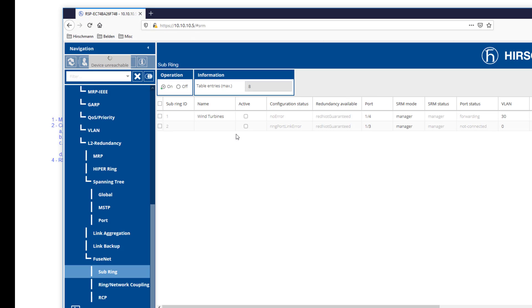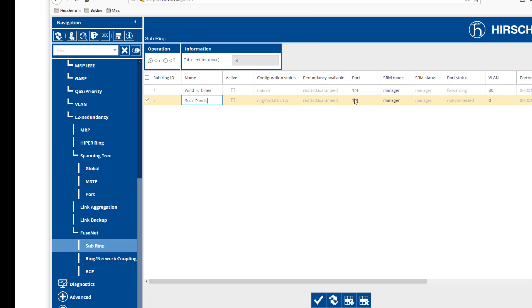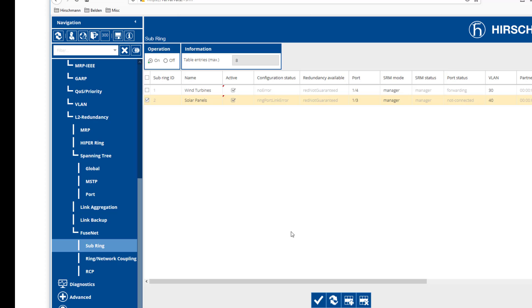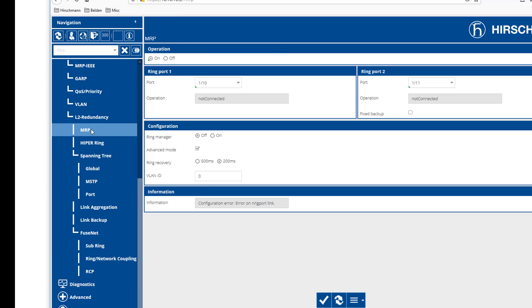Then we're going to create another entry for our solar panels. For the solar panels, it is going to be on port 3 and VLAN 40, and this is also going to be set as manager. We're going to enable this and turn these two subrings as active. So we now have VLAN 30 here, VLAN 40 here, and our MRP VLAN ID being 0. We know for a fact that we don't have a conflict in any of our redundancy protocols.